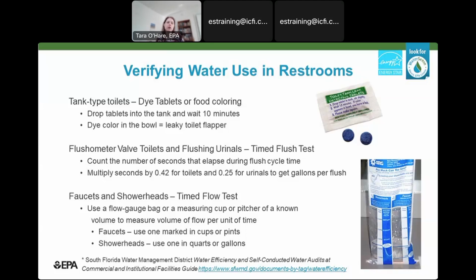With flushometer valve toilets and flushing urinals, you have to time the whole flush cycle. You can actually just count the number of seconds that it takes to go through the whole cycle, and you can figure out if that's an appropriate amount of water for that fixture. So 4 seconds is generally about 1.6 gallons per flush.